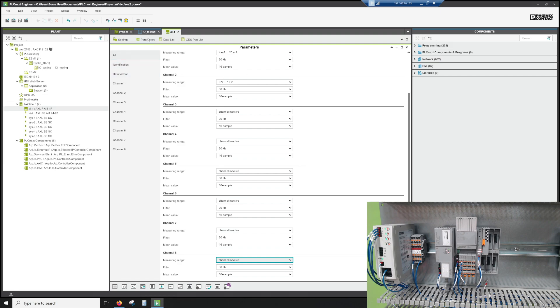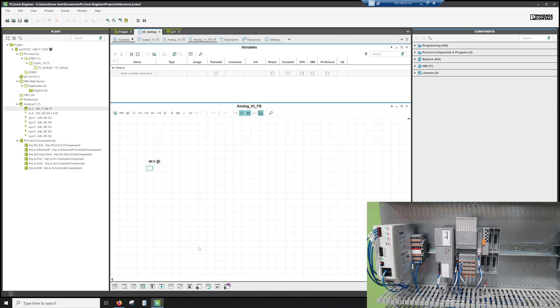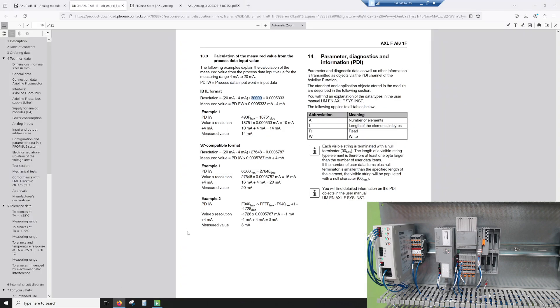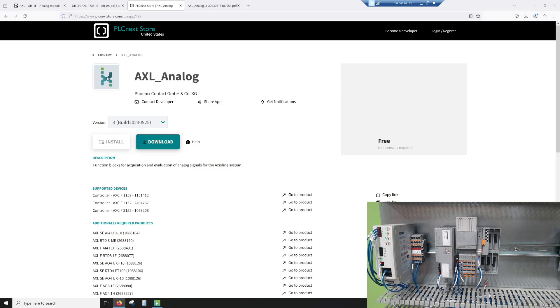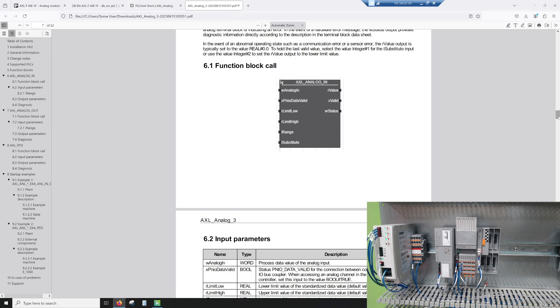Now that all channels are inactive, we'll go over to programming. With the PLCnext you can bring in a library. If we go to the PLCnext store and search for 'analog' in the search box, we get 'AXL Analog' — a library from Phoenix. It gives you a couple of function blocks: scaling in and scaling out. This is a basic block where the analog word in is your input, and there's also a valid signal for use over PROFINET to ensure you have valid data available.